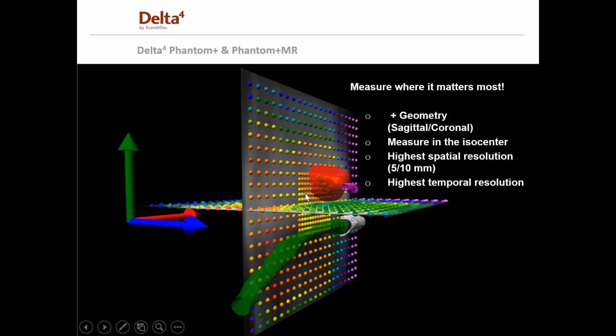We have software in the system that will take two deliveries. You make one delivery, then you offset the Phantom by 2.5 millimeters, do a second delivery, and now you can merge those two together to give you 2.5 millimeters of resolution in that isocentric and high gradient region. In case you have a long field, we can also merge two fields end to end, which gives you a total of 38 centimeters of coverage.